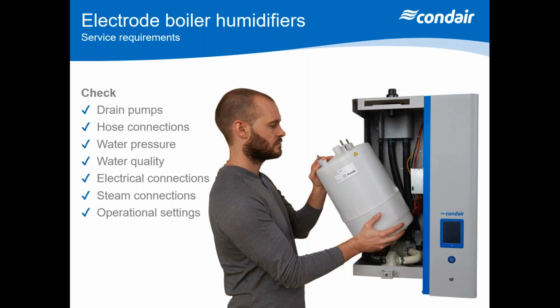Also, water pressure is vital to check, because the valves that allow the water into the unit are set to a certain flow rate. And it's normally about 4 times the boil-off rate that the valves will be set for. This is to keep the water conductivity levels higher to allow you to get the capacity out of the unit. Now, if that flow drops off or is reduced in some way, you're going to find the water levels creep lower and lower in the cylinder. And that's going to affect the electrodes and possibly damage them. I'm sure some of you may have even seen a situation where it has electrically arced across from one plate to the other. That's more damaging to the electrodes themselves, because the zinc coating that stops them from rusting comes away and the mild steel gets exposed and they can literally just erode away. So it's very important that the drain pump is checked and set correctly in terms of dilution drains.